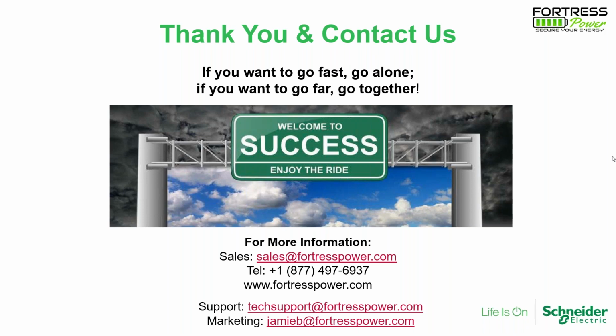Okay. What are the operating and charging temperature ranges for the battery? I don't have the number off the top of my head, but it's in our technical spec and installation manual. I'll give you a few hard stops. Once your temperature is under 32 Fahrenheit, you should never charge the battery. The battery will start generating a lithium plating effect, which will permanently derate your batteries. So 32 is a threshold. Usually, I think I remember it's from around 45 all the way up to 110. That's the range we say you can operate the batteries. But one thing I want to point out: it's not a good idea to charge your battery under 32 in any situation.